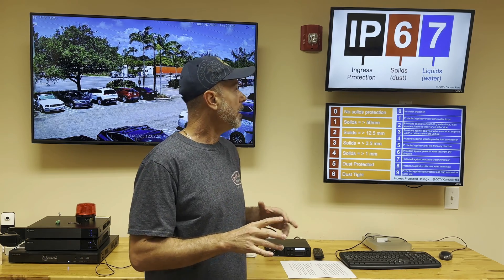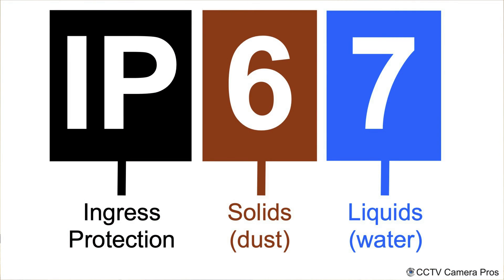IP stands for ingress protection, and the IP rating system was developed by the International Electrotechnical Commission. They developed this standard way of grading how weatherproof or how resistant an electrical enclosure is to solids and liquids — in particular dust and water. The IP rating system consists of the prefix IP followed by two digits: the first tells you how resistant the enclosure is to solids, and the second digit tells you how resistant it is to liquids or water.